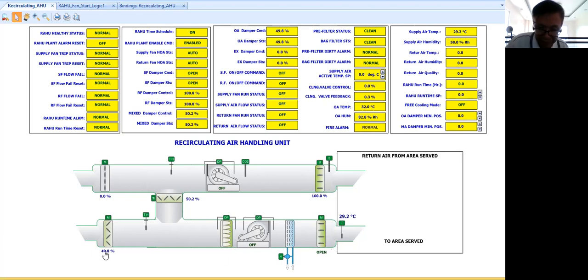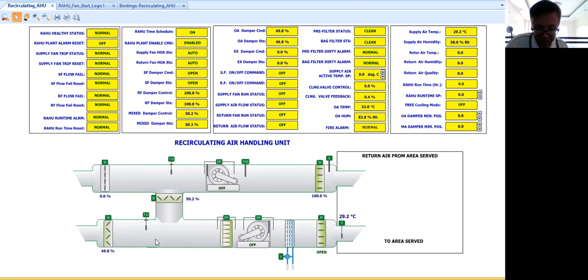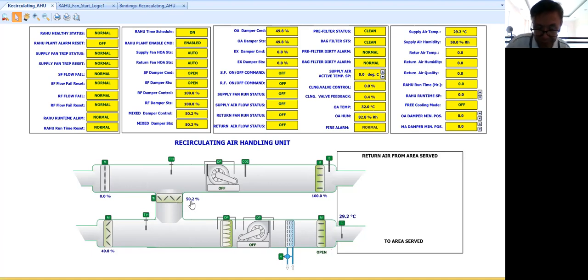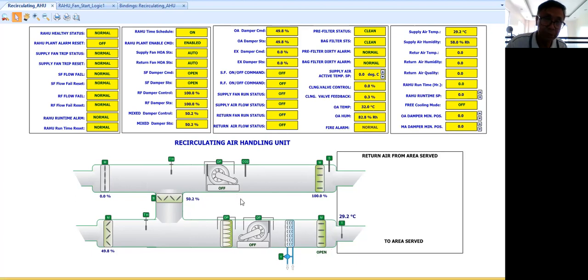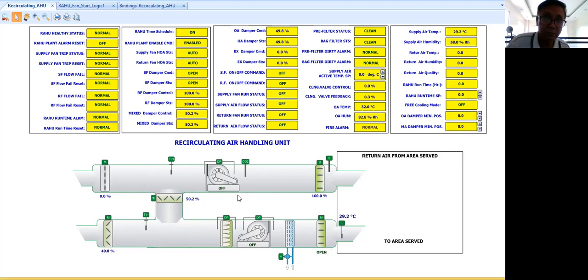Then I tried to open my outside air initially at 50%, almost 50%. Likewise for the mixed air 50%. Now guys, for this dampers opening, you can always coordinate with the mechanical people who are checking or who is responsible for the air balancing because they will be the one to give you what will be the...